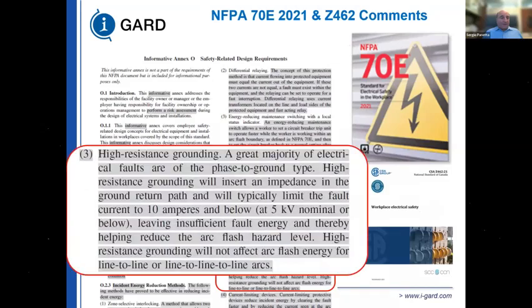So if we look at our electrical standards for safety, high resistance ground, a great majority of electrical faults, this is what I said earlier, high resistance grounding is an arc flash mitigation technique. Now, this is where we have to have some differentiation. It does not lower incident energy.